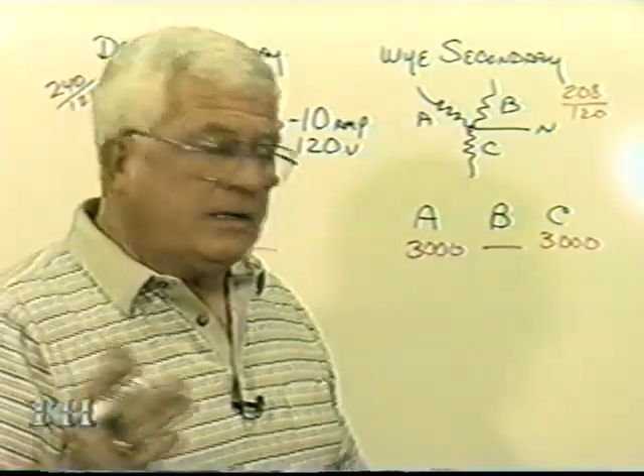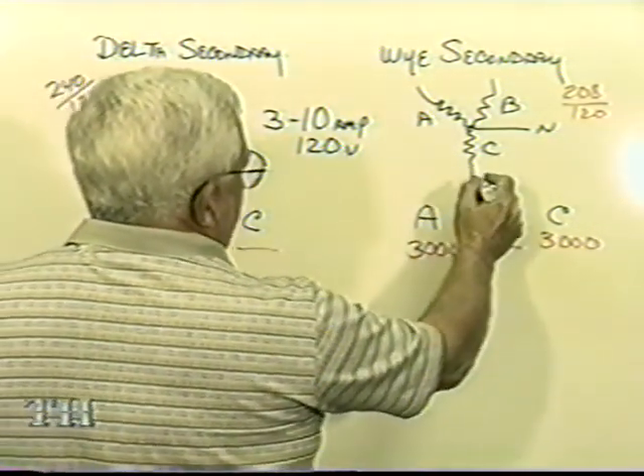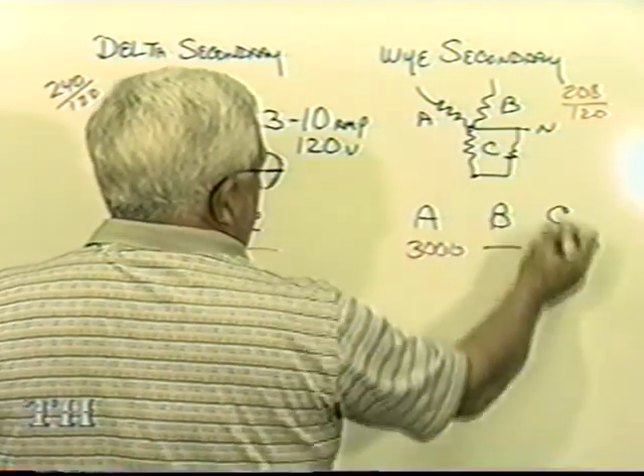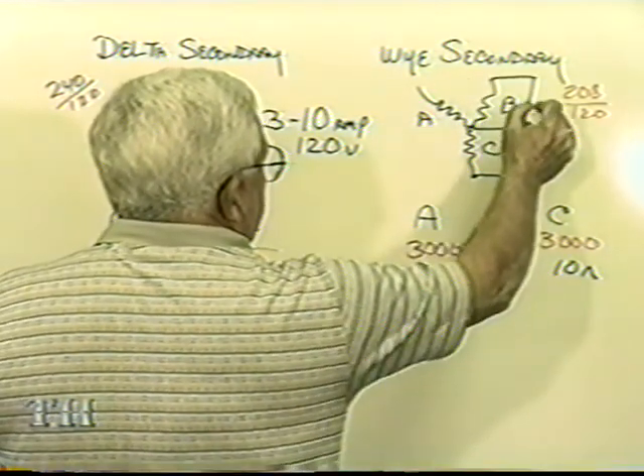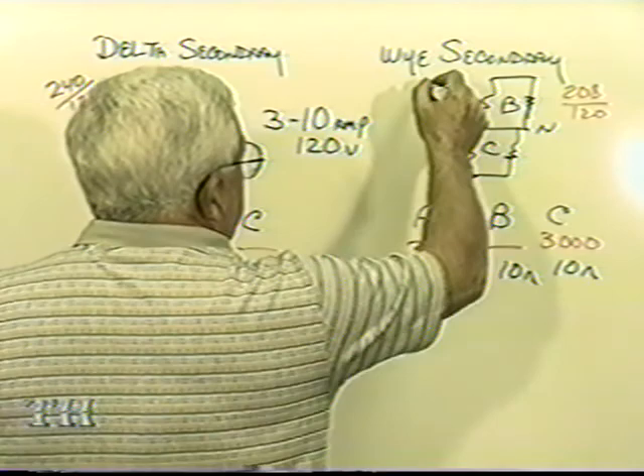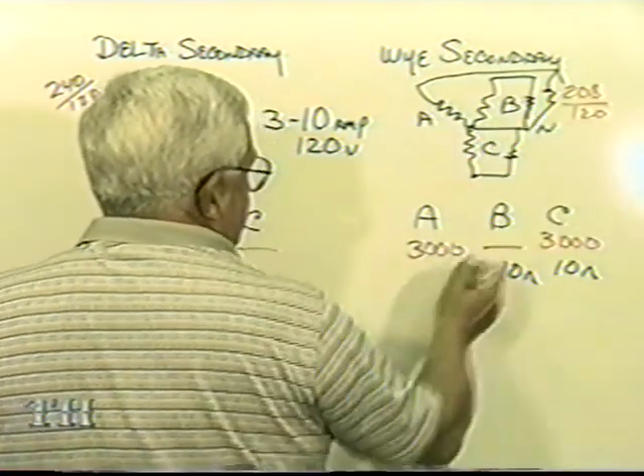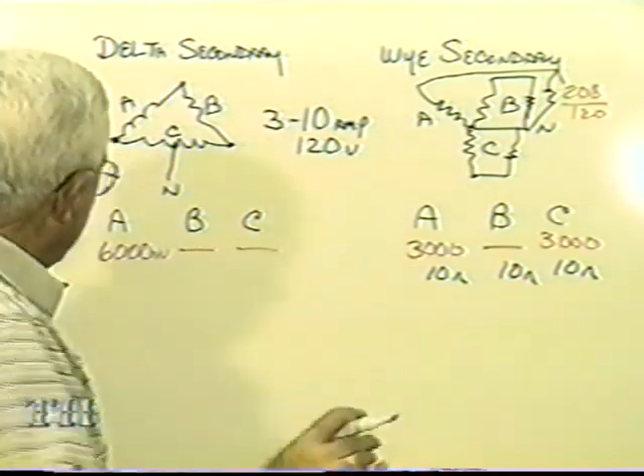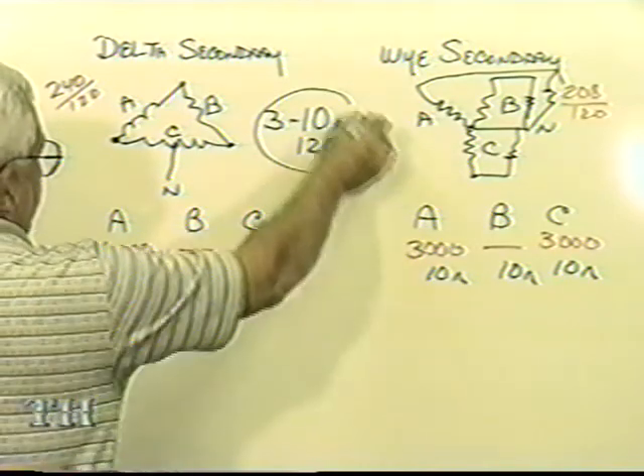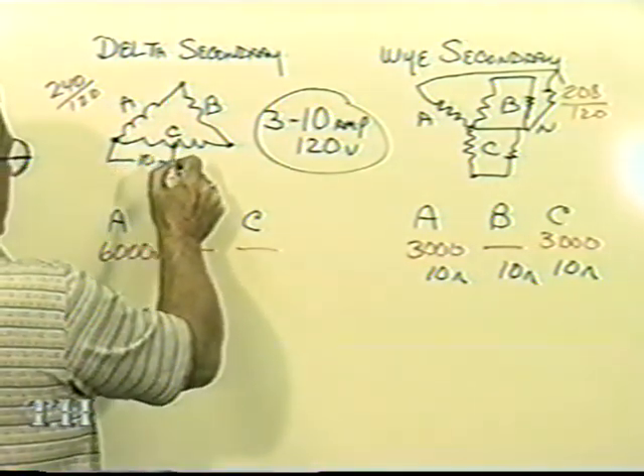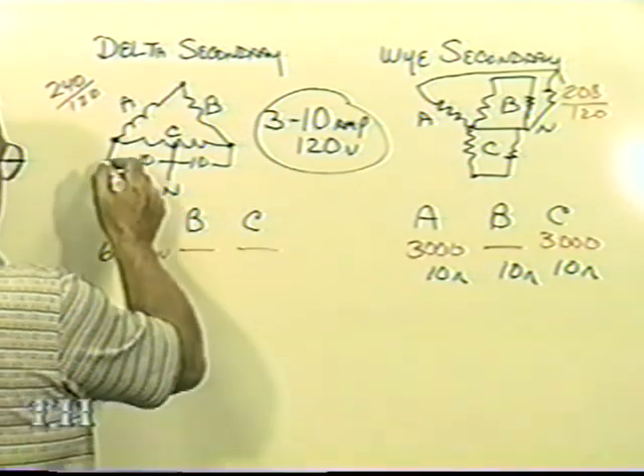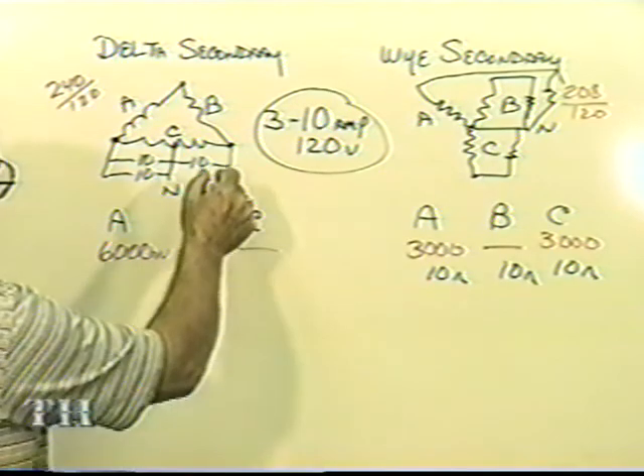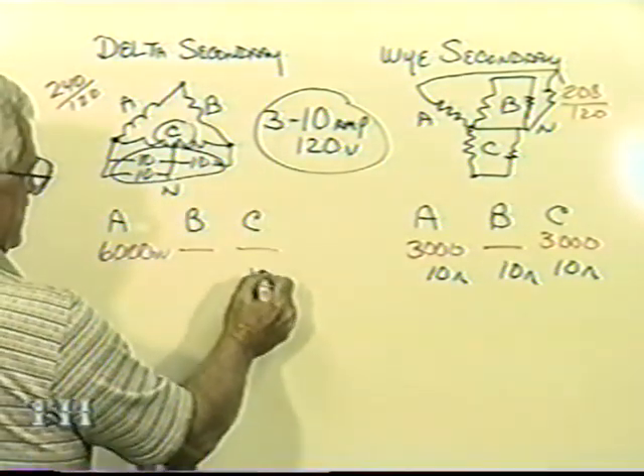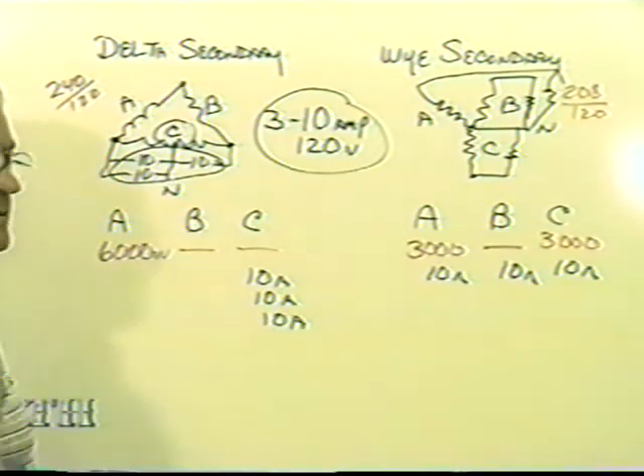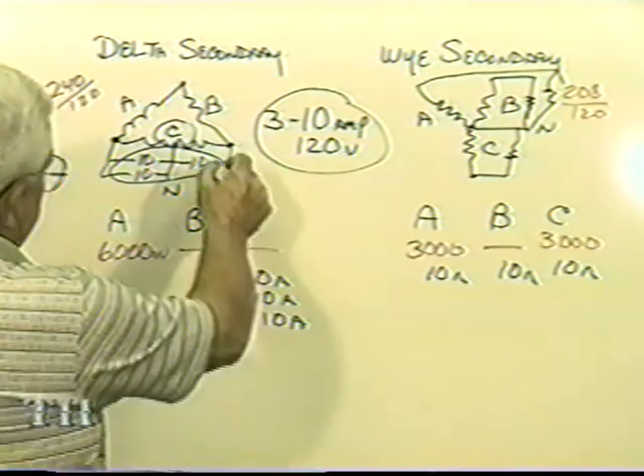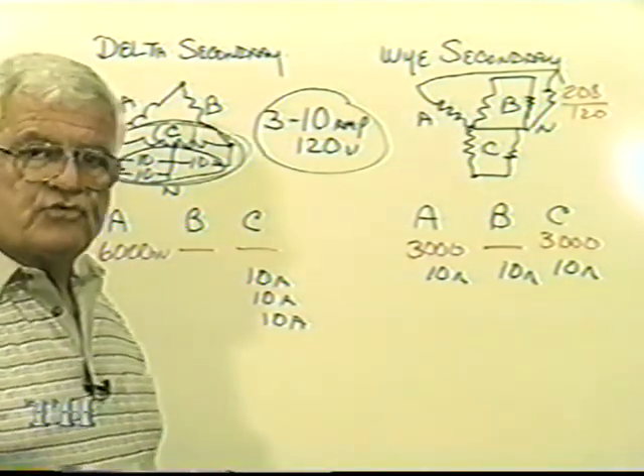With these 120 volt loads, I can come from C to neutral, 10 amps. I can come from B to neutral, 10 amps. I can come from A to neutral, 10 amps. But watch, when I come over here with these same 3 loads, I have to come 10 amp, 10 amp, 10 amp, but all 3 loads are on transformer C. Transformer C is the only one that has a neutral conductor.